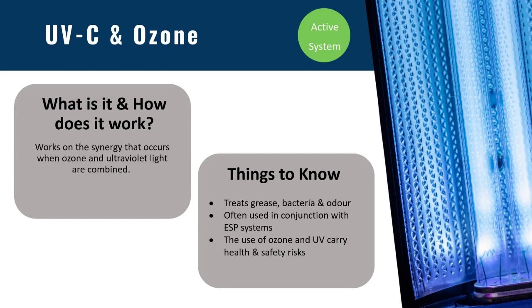risks, though. It should be noted ozone systems carry inherent risks from the toxic nature of the high ozone concentrations within the ductwork, and there is potential harmful exposure to high intensity UV lamps. The system should never be on when the fan is off, and therefore the systems require protection interlocks, air pressure switches and signage. The capital investment required is considered medium to high.